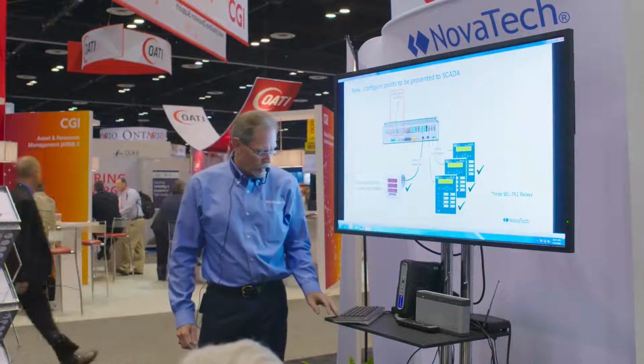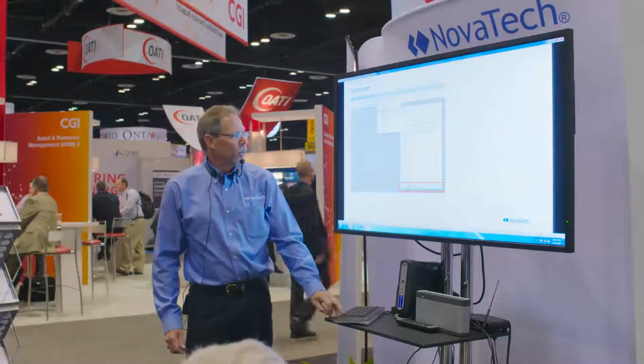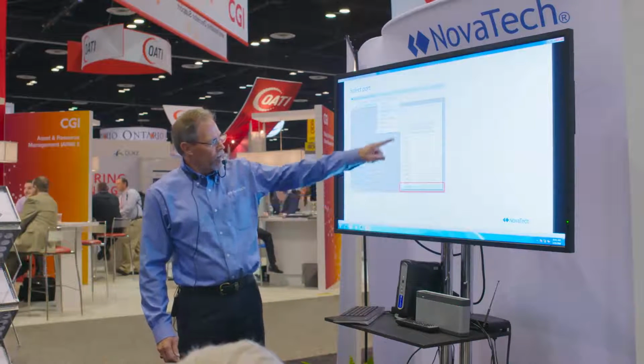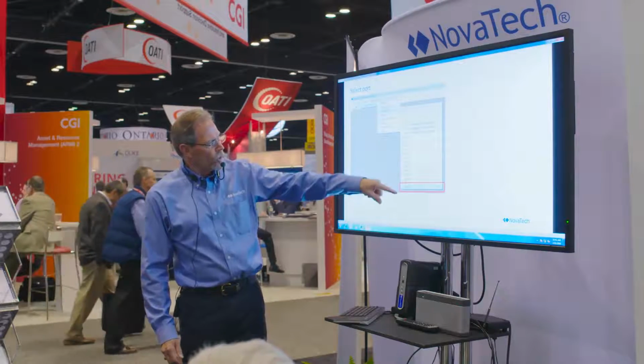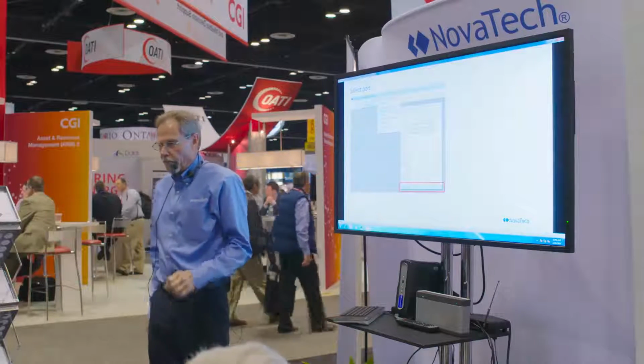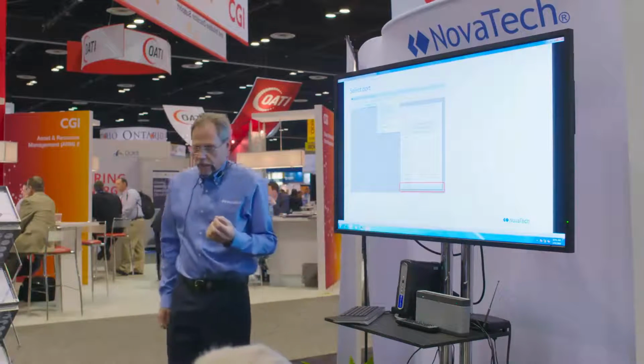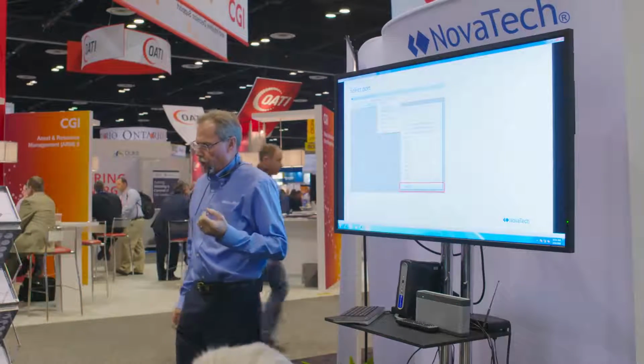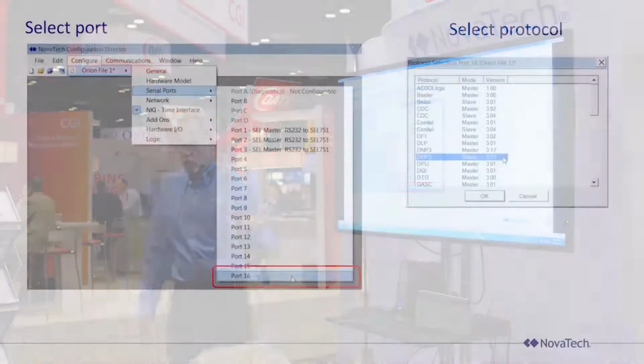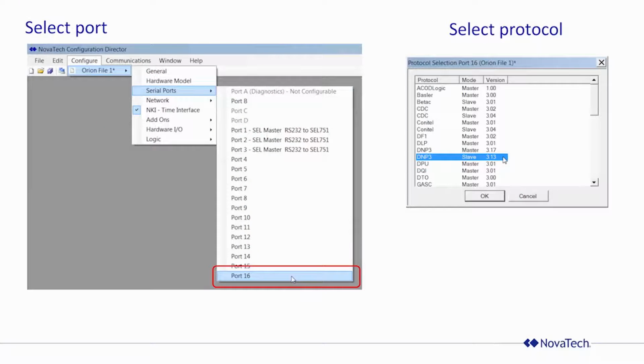The next thing I want to do is set up my slave port. So all I'm going to do here is define a port. It could be any one of those 16 ports, or it could be port B. Port B on the back has the option to be a modem port. So if you've got a Bell 202 or an old 4-wire lease line modem that you want to connect, that's usually the port that people use, because that also supports all of the modem handshaking commands and what have you. But you can put it on any port.